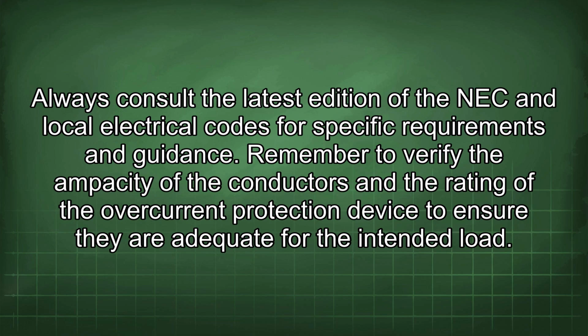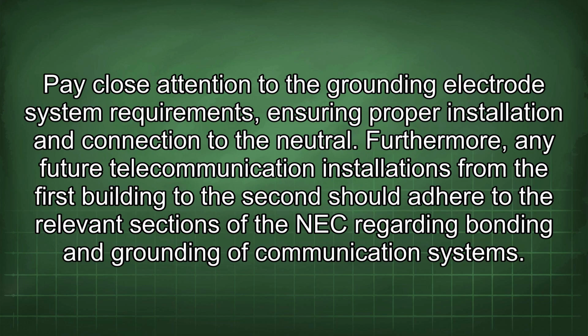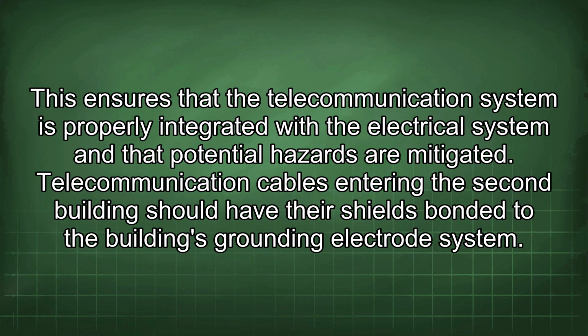Remember to verify the ampacity of the conductors and the rating of the overcurrent protection device to ensure they are adequate for the intended load. Pay close attention to the grounding electrode system requirements, ensuring proper installation and connection to the neutral. Furthermore, any future telecommunication installations from the first building to the second should adhere to the relevant sections of the NEC regarding bonding and grounding of communication systems.